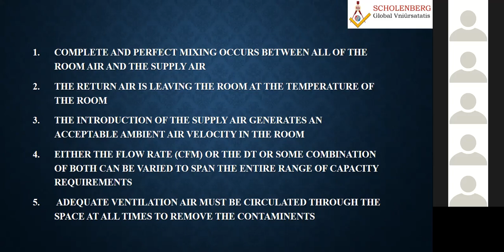It depends: if in one corner there is a wall, a glass, directly exposed to the west side, the temperature there will be slightly higher, 23.5. And on this side, it will be 23. If you go to another corner, it may be 22.5. Another one is 22.8. And the center will be 22. So you have to measure everything and take the mean. This is what the ASHRAE standard says. Similarly for flow rate, when you are using the anemometer for measuring. So these are some of the assumptions when we go for that.